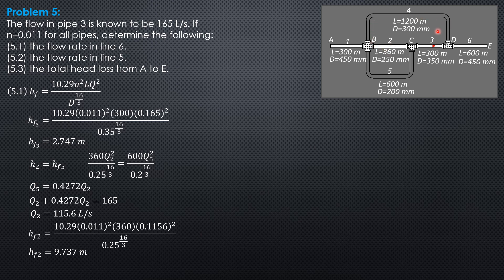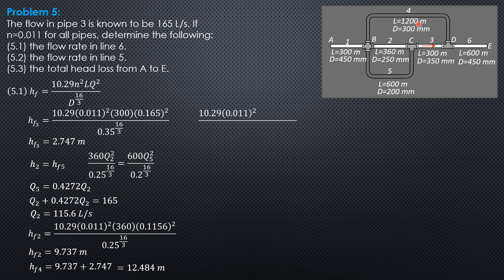Then we can now compute HF4. HF4 is HF2 plus HF3: 9.737 plus 2.747, which equals 12.484 meters. Knowing HF4, we compute discharge Q4: 10.29 times 0.011² times 1200 times Q4² over 0.3 to the 16/3 equals 12.484. So Q4 is 0.1166 cubic meters per second, or 116.6 liters per second.